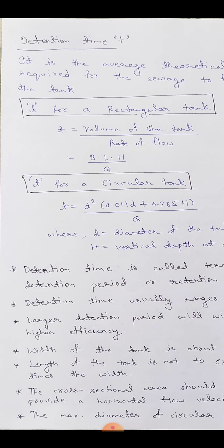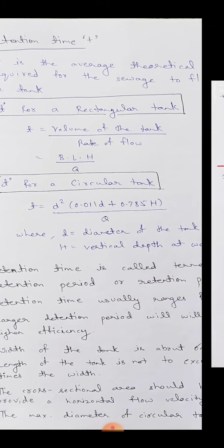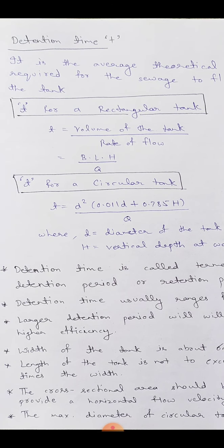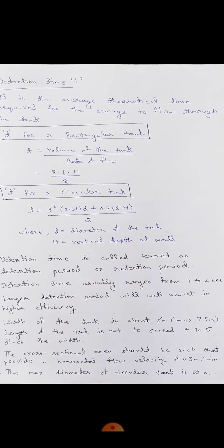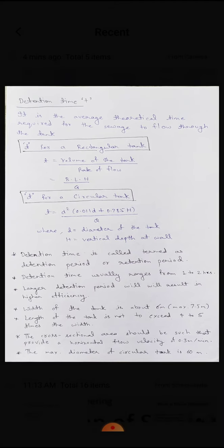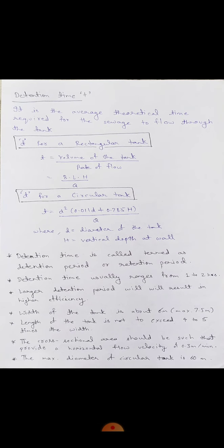Then next is the width of the tank is about 6 meter. Okay, you have to keep the width of the tank till 6 meter, that is maximum 7.5 meter. It should not exceed 7.5 meter, but as an average value you can take up to 6 meter.